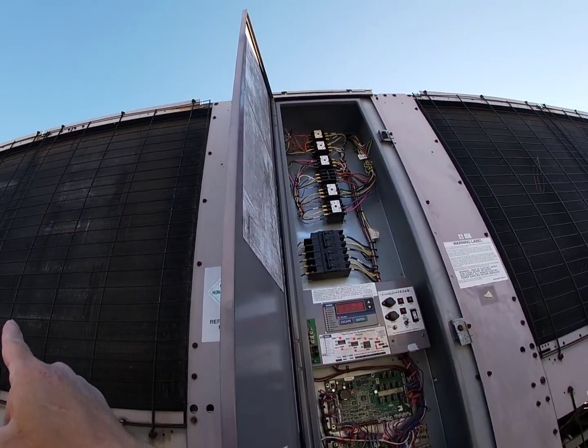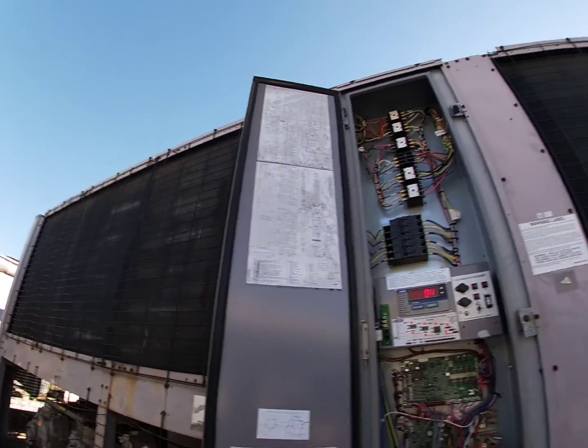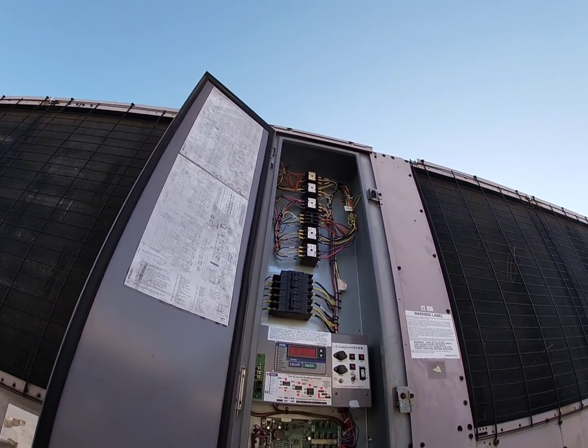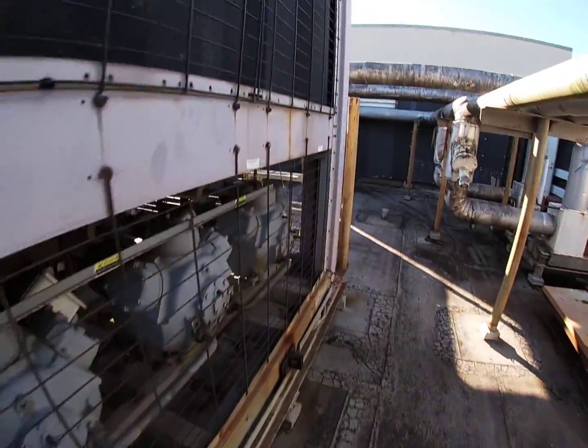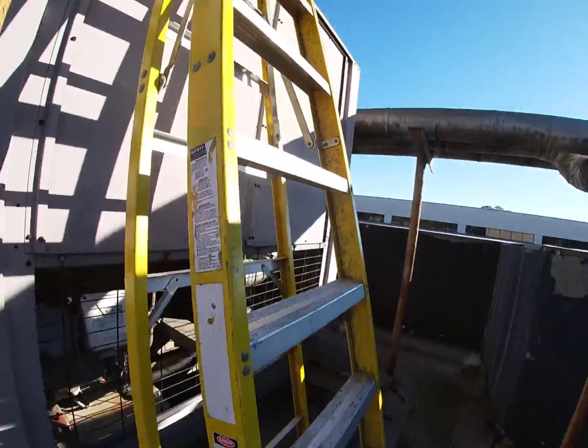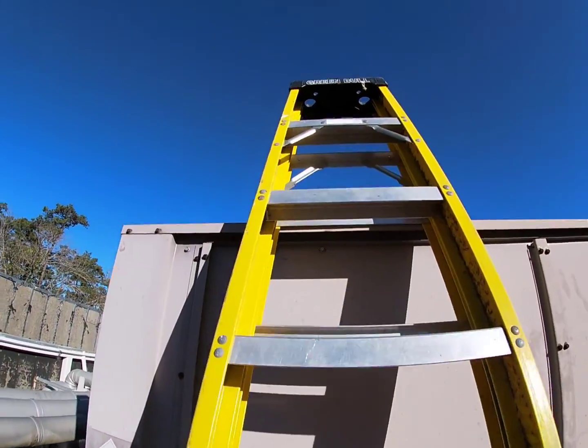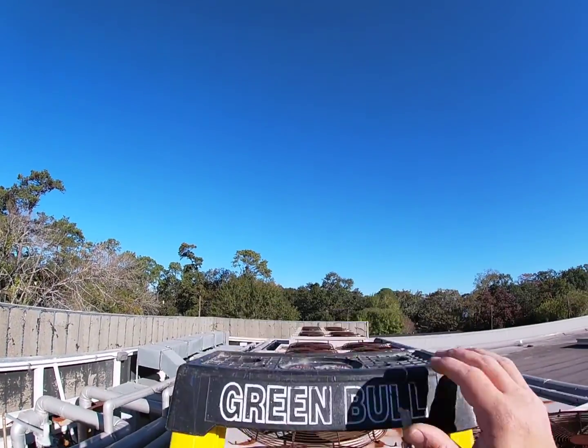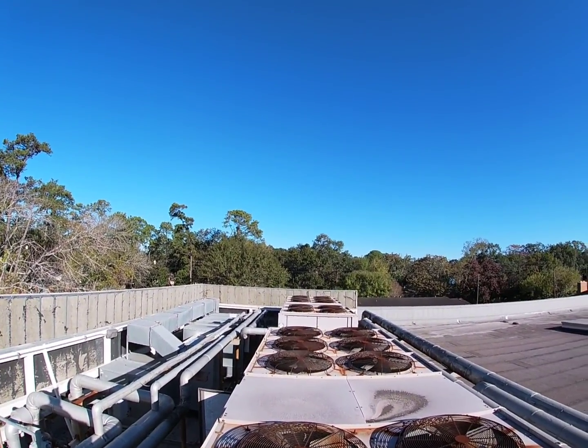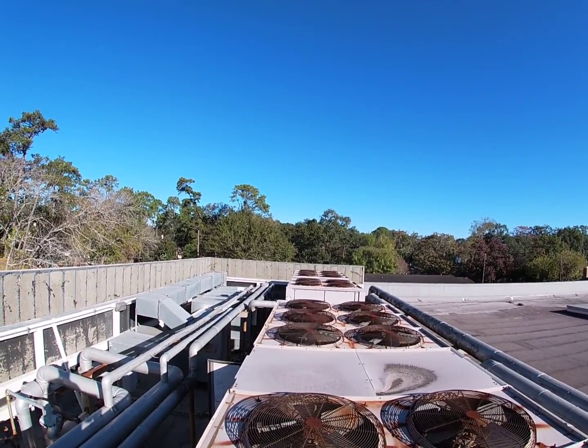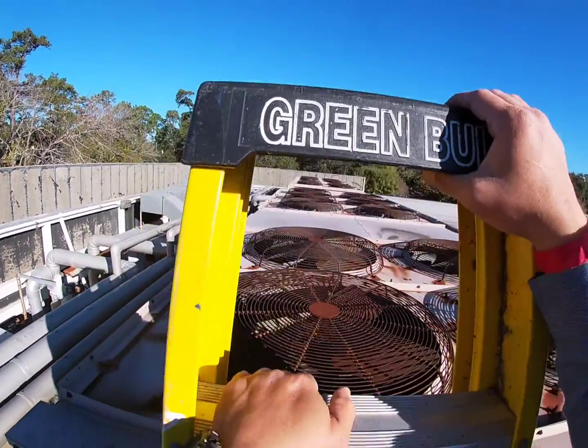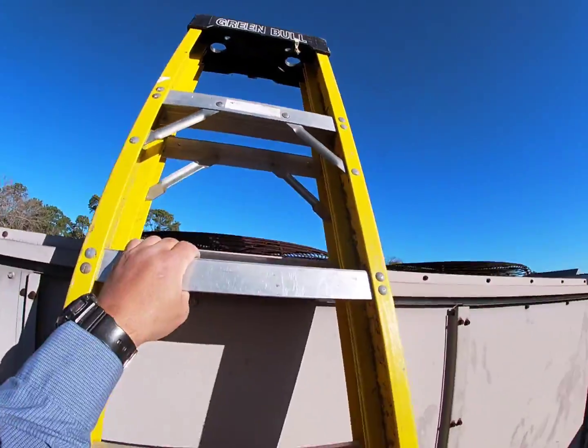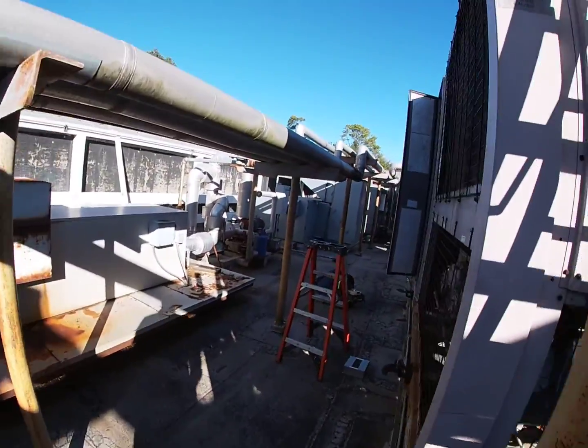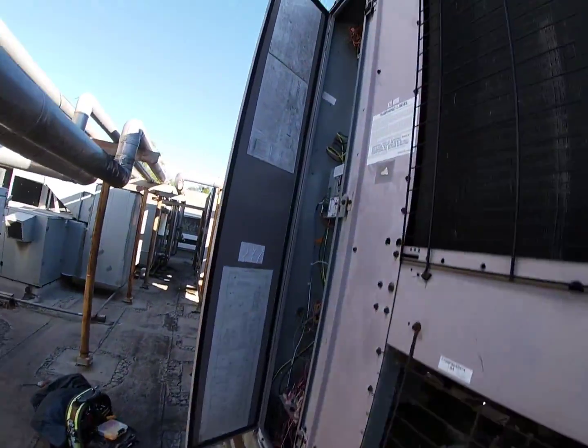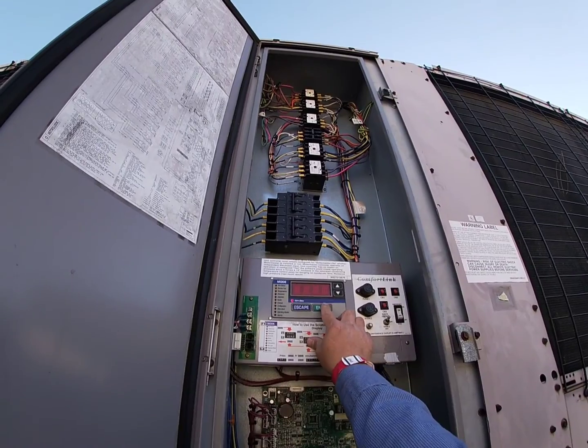That motor sounds like it's got bad bearings in it, but I think that's the contactor. Oh, that's the one that we're working on there. That second one, so let's take a quick peek at that. Yeah, she's running. Yeah, that's the one. Yeah, she's running, so yeah, I guess this is the only problem they got - this one motor here. So this motor should be on, but since it's grounded and we got it disconnected, it's not running.